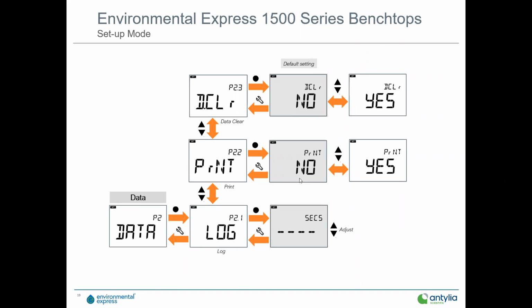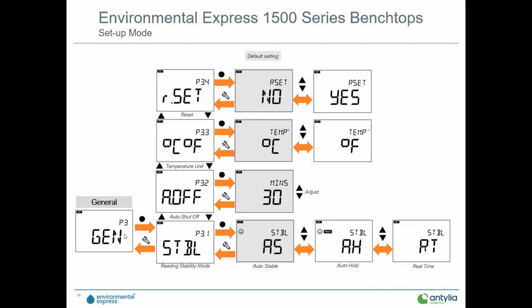The defaults are listed right here: no to clearing data, no to printing, and then you can do your auto adjust. And then finally, the general program. Now this allows you to get into stability mode. You can set up with auto stable, auto hold, or real-time measurements. Again, you back out of this using the settings key.